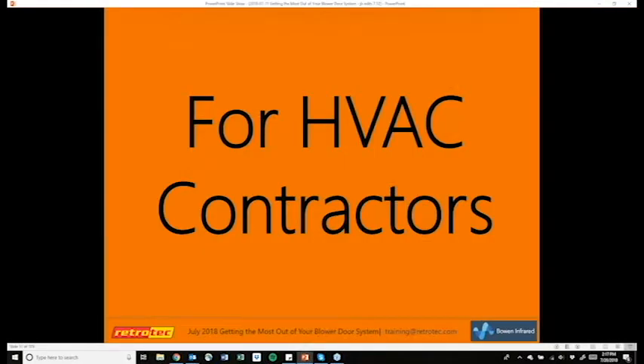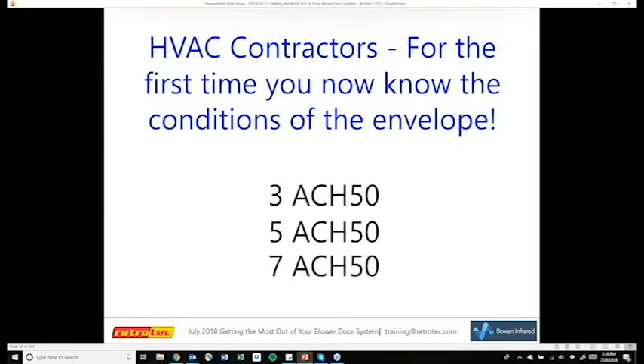So what does this mean for HVAC contractors? Typically when we think blower doors, we think HERS raters, BPI people, and energy auditors, but this is a big deal for HVAC contractors as well, especially for those of you that are familiar with doing HVAC load calculations. If you're familiar with those calculations and the software involved, such as Wrightsoft or Elite, you have to enter in the infiltration of what the house is going to be. And a lot of times people just wing it. They say it's average. You have choices from terms such as loose or tight or semi-loose or semi-tight. And without actually testing the envelope, you really don't know what you have.